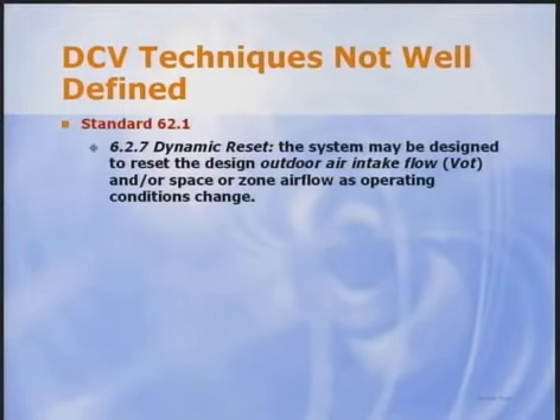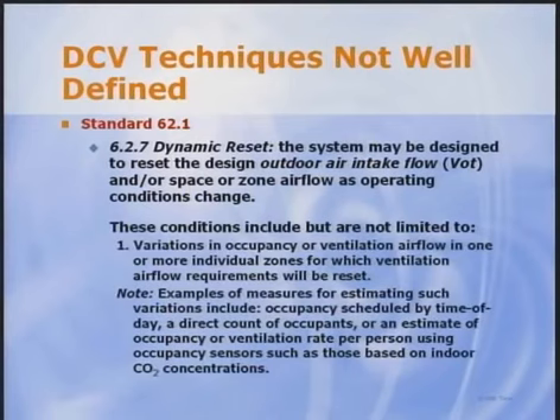As Dennis pointed out, Standard 62.1 allows dynamic reduction of outdoor air rates not only when occupancy is below design, but also if any design condition used to determine the outdoor air rate changes. Dennis discussed various control options that designers might use, but the most common dynamic reset approach is demand control ventilation, and is the first application example listed in section 6.2.7, although the term demand control ventilation is not used. Several examples of DCV are listed, such as scheduling ventilation based on expected occupancy schedules, using people counting devices such as turnstiles, and using CO2 concentration. Not listed but clearly an option are occupancy sensors.